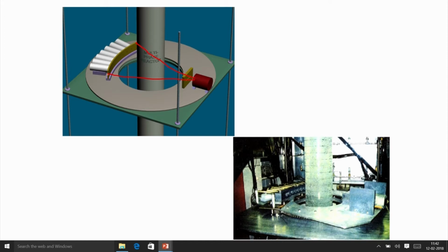Okay. Now, what happens with this beam, you put several detectors like here, whatever you can see here, each detector will see one line, each detector can see one line this way. Okay. Now, what you do, there is a moving carriage, if you see this carriage, this table can move in r and theta direction, you can say this is mostly theta motion. So, this carriage will move in this way. So, you will be able to scan with the r, with different theta.